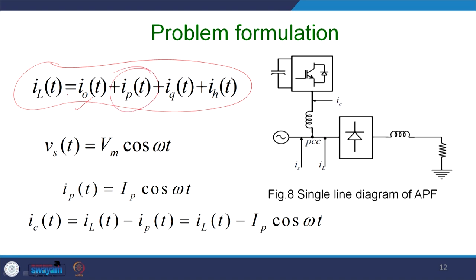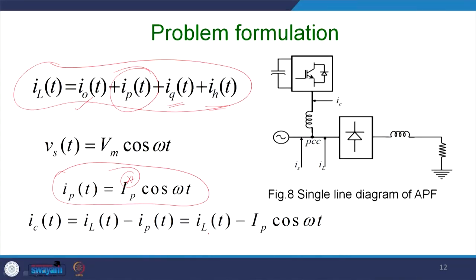IP is the in-phase component of the current with the voltage, and IQ is the quadrature-axis current. All harmonic currents are represented by this. We shall see that Vs = Vm cos(ωt), so we expect that the in-phase component Ip = Ip cos(ωt). The compensating current Ic will be IL minus Ip, so you require to calculate this entity very accurately by the reference generation technique, and thus you get the compensating current: Ic = IL minus Ip cos(ωt).